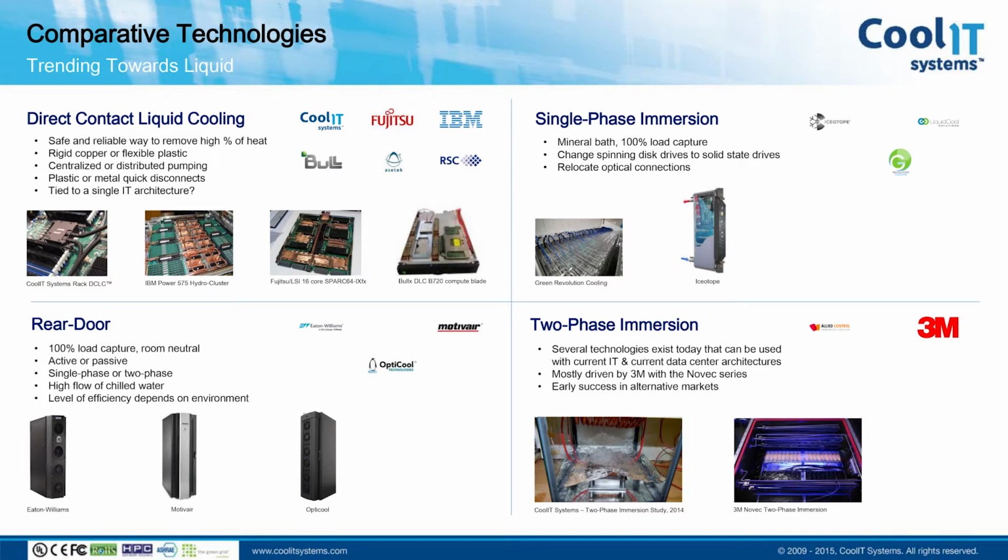And how much cost does this add? Just sort of a ballpark. I'm sure it's different in every situation. Yeah, sure. So it depends. If we look at a standard 1U server, our kit per server is somewhere in the neighborhood of $90 to $100 typically. Okay, so per server, and then the cost of the heat exchanger would be amortized over how many servers you connect to it, of course. Exactly. And we have a number of different heat exchangers dependent on whether it's a low volume cluster of a few racks. We have rack-based heat exchangers, but if you go to an entire aisle or row, we would have a larger heat exchanger that would serve those. So cost in that area really does depend on which heat exchanger you select.